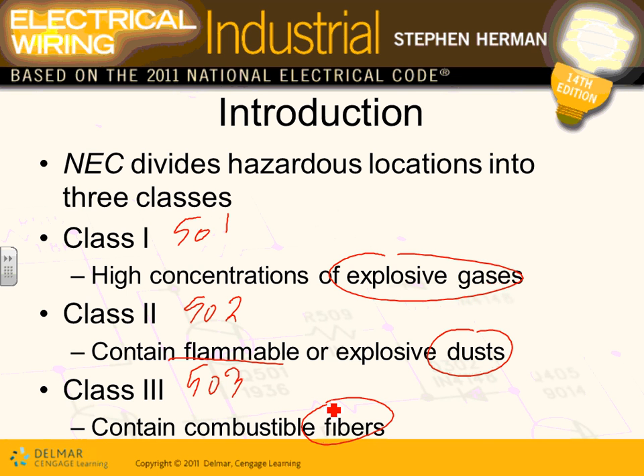Any comments, guys? Any questions about these three locations? So who classifies them, Derek? The engineers and the architects and the fire marshal guys are the ones who classify these. So they walk into this area based on whether the gas or the dust or the fiber exists. They classify it as Class 1, Class 2, and Class 3. Who cares? The question would be, Karen, who cares about these classifications? If it's Class 1, you have to use certain wiring methods. If it's Class 2, others, and Class 3, a third wiring method. So the wiring methods will change. For example, in a Class 1 Div 1, I can't use EMT conduit even if I want to.